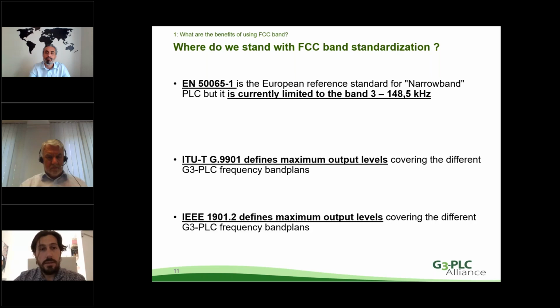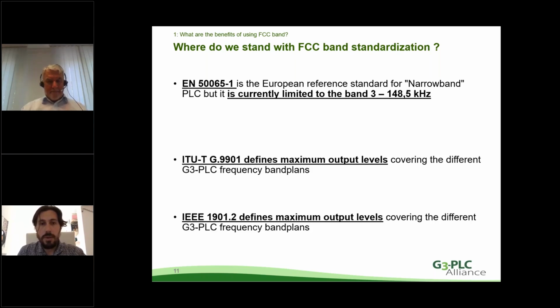In addition, you have ITU-T G9901, which is one standard that defines maximum output levels covering the different frequency bands of G3-PLC. We also have an IEEE standard called 1901.2, which also defines maximum output levels, but also some methodology, as explained afterwards, which also covers the different G3-PLC frequency bands.